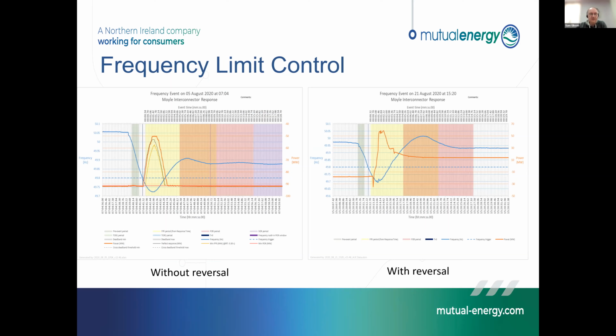And we offer that across the complete range of DS3 services from FFR through to the tertiary offerings. We have a response there in the low hundreds of milliseconds. And that service is a really elegant part of what we can do for the network. But on the right-hand side, you can see the situation where we have to have a power reversal. That's a messier response. We still respond very quickly, but it's not the clean, dynamically matched response that the system operator would prefer to see. And that's one of the key things that we'll address in the control system upgrade.